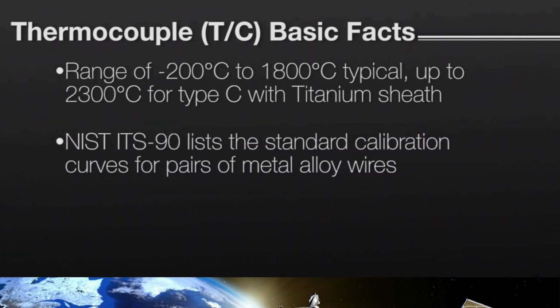The United States National Institute of Standards, which we call NIST for short, publishes a ghoulishly long standard called ITS-90. It lists the thermoelectric voltage for every pair of thermocouple alloys at intervals of 1 degree C. You can download it for free and use it to create table lookup software for measuring temperature with thermocouples.